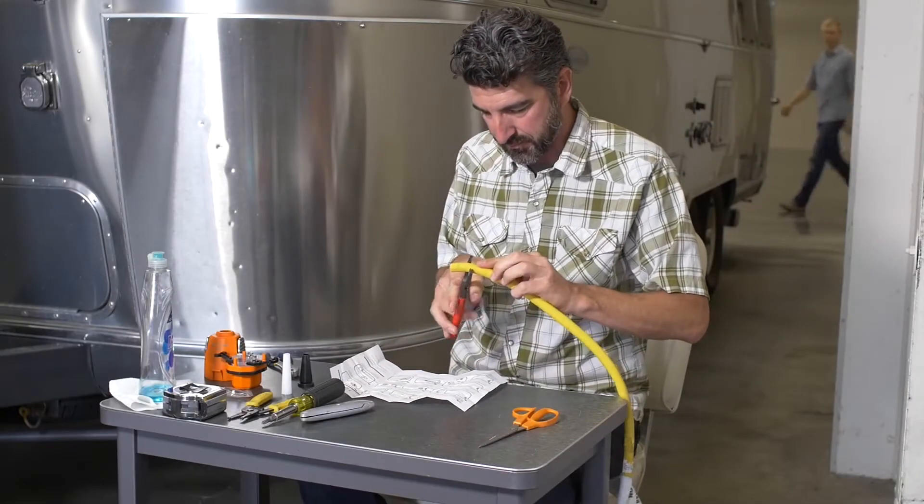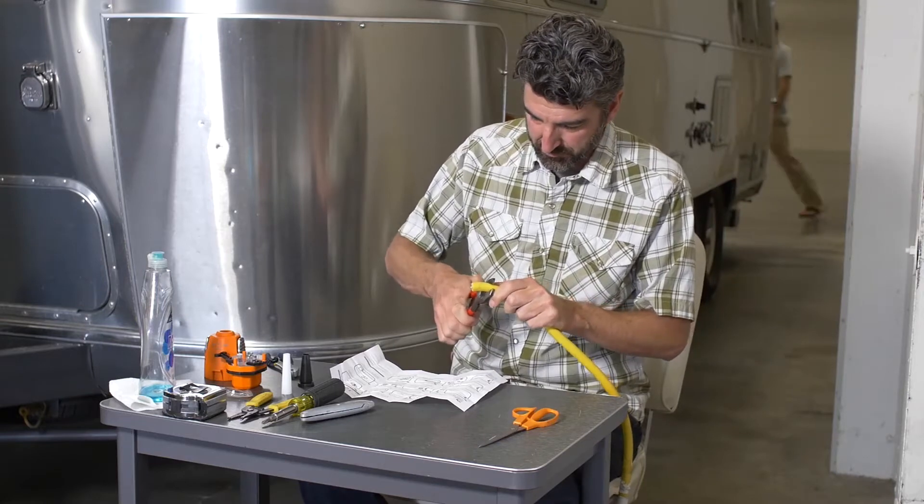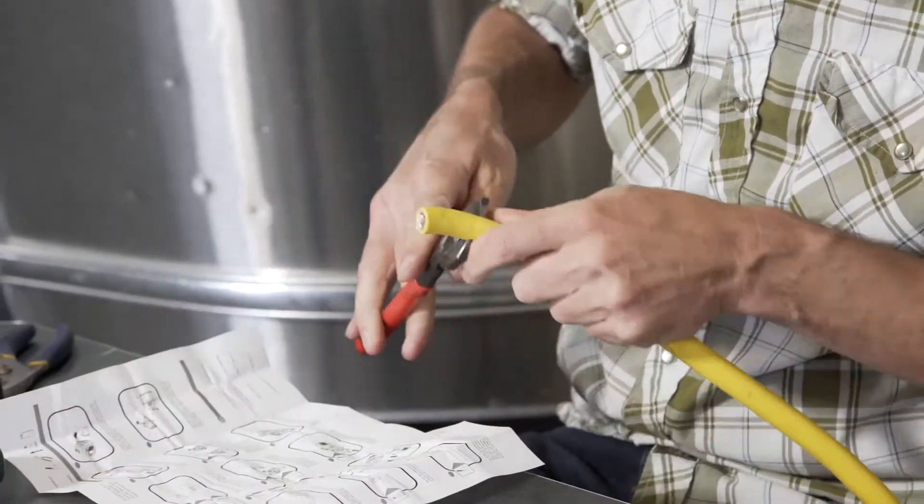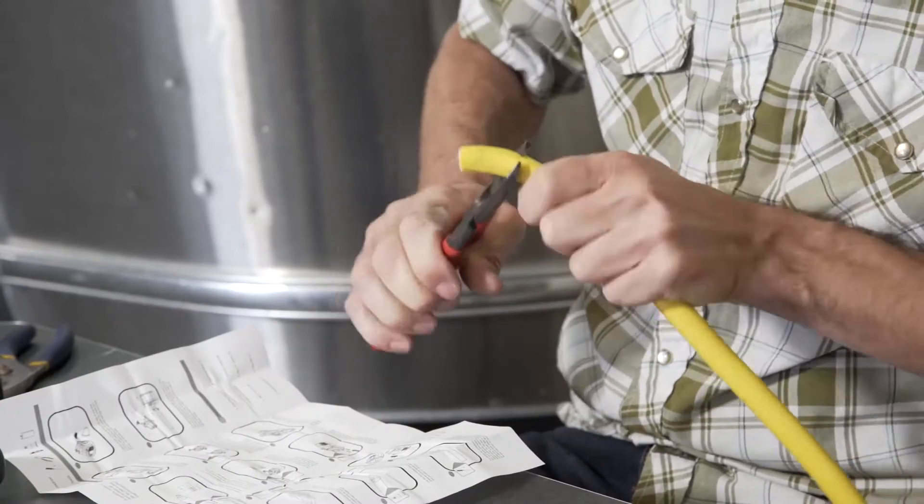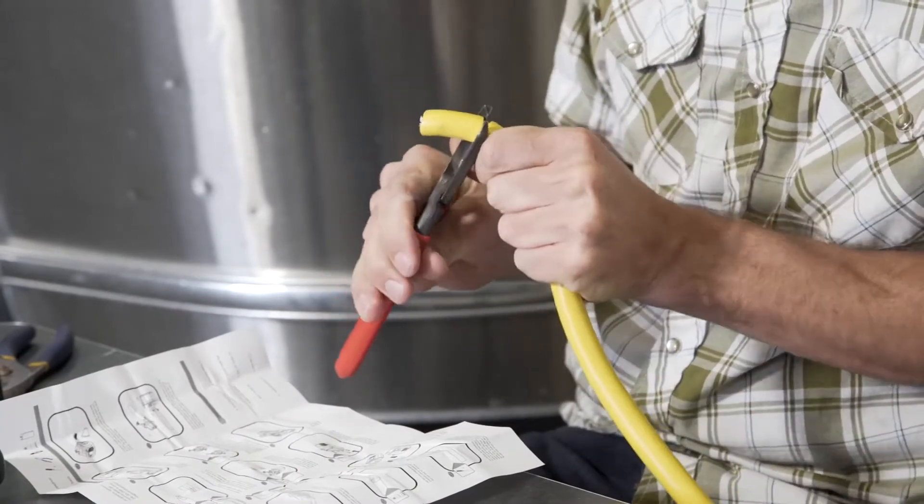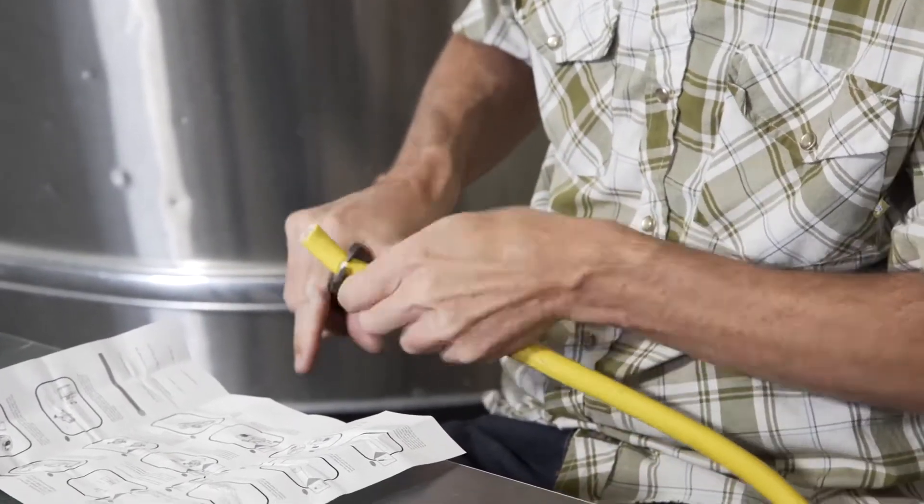Measure one and a quarter inches back from the freshly cut cord end and use marker to indicate where to cut. Then, lightly score the outer jacket with a utility knife and be sure not to cut any of the inner wires. Remove only the inch and a quarter segment of the outer jacket, exposing the inner wires and the fibrous cord filler.